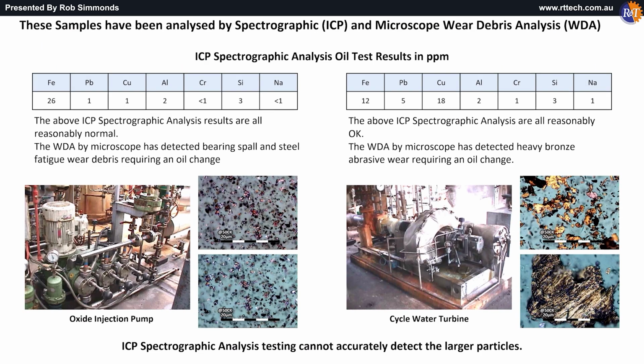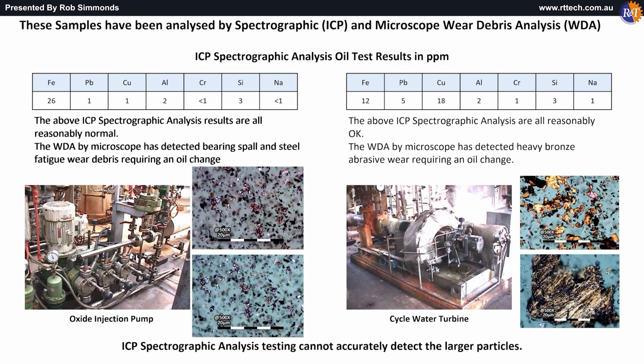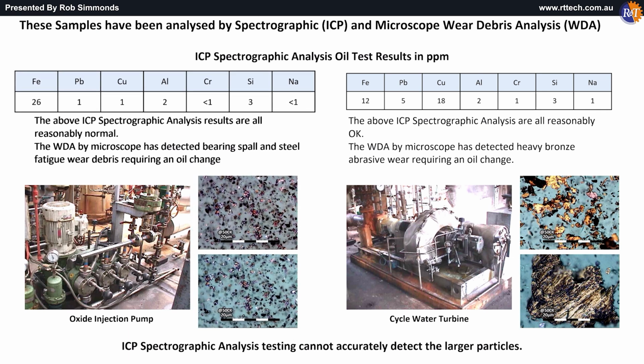These samples have been analyzed by spectrographic and microscope wear debris analysis. On the left, we can see the above ICP spectrographic analysis results are all reasonably normal. But when we check below, the WDA by microscope has detected bearing spall and steel fatigue wear debris requiring an oil change. Note how these particles were not detected in the ICP results.